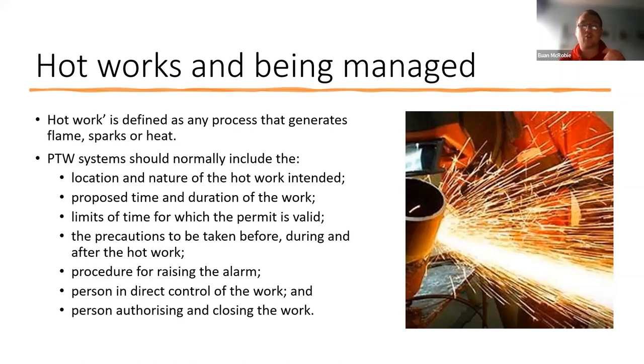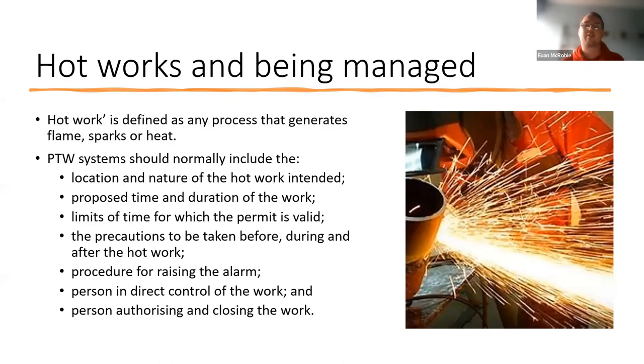Hot works permits should be closed out at least one hour before the site or premises closes for the day — so if you finish at 5pm, any hot works should stop at 4pm to allow that fire watch period and prevent residual flames causing a fire. For timber frame buildings it's two hours, due to the potential for small sacrificial timber ignition within the timber frame. Ensure all permits are signed off and closed out.